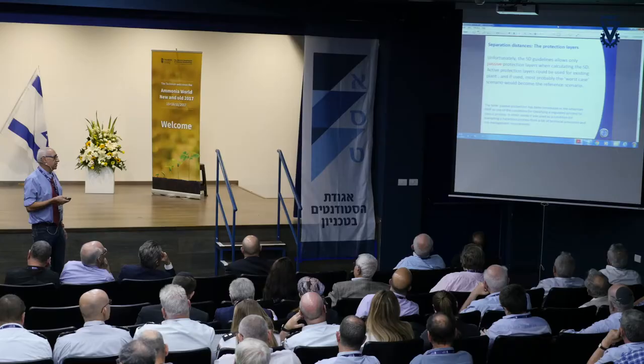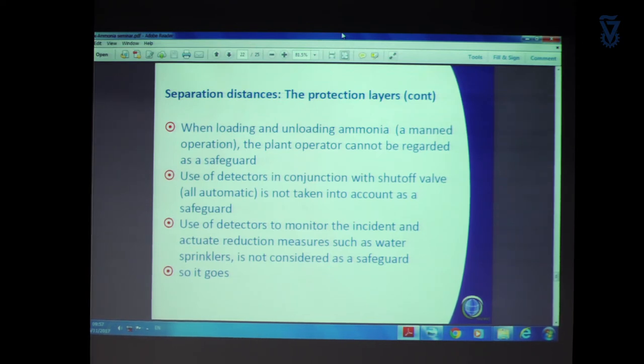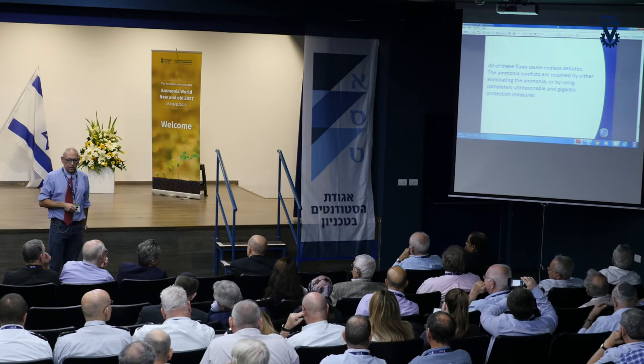Spills over water, short-term operational faults like loading and unloading, are also not handled adequately. And finally, the protection layers are taken to be only passive when calculating safety distances. For ammonia, this gives no credit for loading and unloading being a manned operation — a person can do something when a leak occurs. Use of detectors in conjunction with shutoff valves, which is an automatic system, is not credited for separation distances. And use of detectors to monitor incidents with actual reduction measures like water curtains or sprinklers are also not credited — unless you take the worst-case scenario instead of the operational scenario.